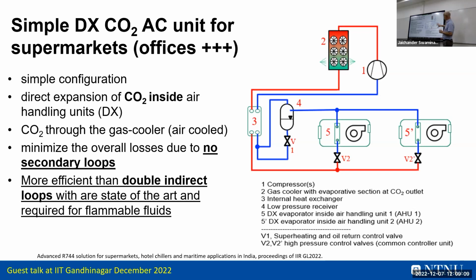What we can do is go straight with CO2, DX into the air handling units, and we can do the heat rejection to the ambient, also directly with CO2. It's non-flammable, it's easy. And we can use a little bit of water on the last part of the heat exchanger, really to use that wet bulb temperature to subcool it before we do expansion. And we calculated back and forth, and we found out that on an annual basis, the energy consumption is equal compared to the double indirect system with an HFC unit. And we did not use any fancy ejectors or anything. It's just a simple one.